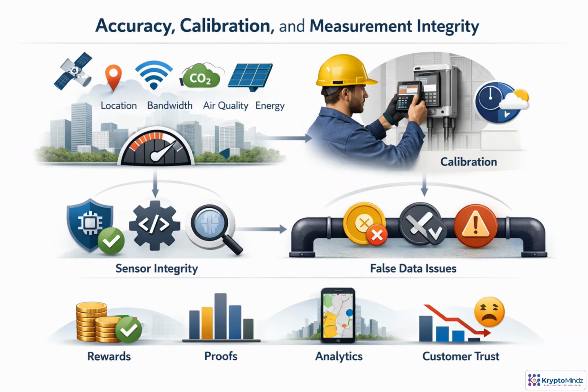Measurement integrity starts before deployment. First, define how accurate each reading must be for the use case. Then choose sensors that can reliably meet that threshold. Calibration sets the baseline, but it is not a one-time task. Devices drift as conditions change, firmware updates, or components age. Ongoing validation helps flag suspicious readings, so operators can recalibrate or replace equipment before bad data affects rewards, proofs, analytics, or customer trust.